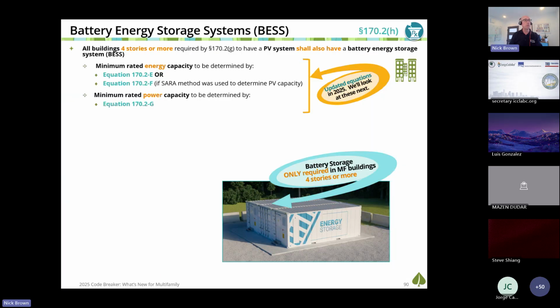Now, battery energy storage systems, notice that solar section didn't change a whole lot, but these battery equations have changed a little. In the last code cycle, you took the solar calculation answer and plugged it into the battery equations to calculate your battery size. Now you use conditioned floor area, which makes everything a little bit simpler. Remember, battery storage only applies to high-rise multifamily, 4 or more habitable stories, and non-residential buildings, I should say. And if you use the CFA method for solar, you use equation 170.2e for battery. If you use the SARA method for solar, you use equation 170.2f to basically downsize the battery size by the same percent that you downsized the solar size. I'll show you that in a second.